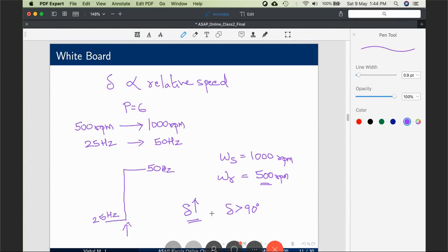Is the concept clear? So, what I am trying to say is that if you increase the frequency in a stepped manner, there is a definite possibility that the machine can go into instability. This is one drawback of the true synchronous mode of operation. Instability is an inherent feature of true synchronous mode. So, what is the workaround?